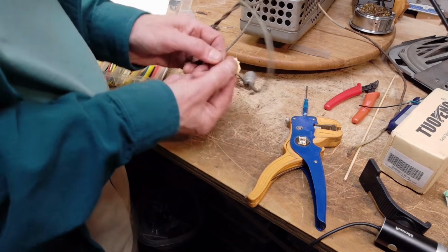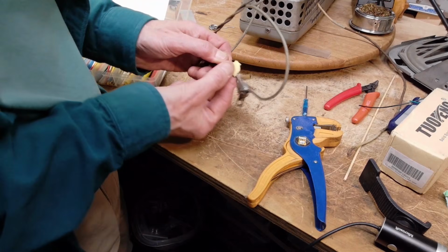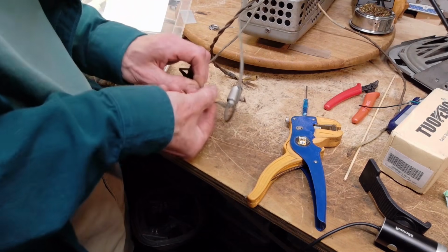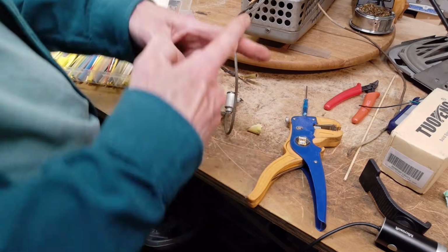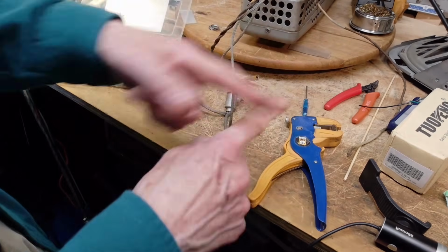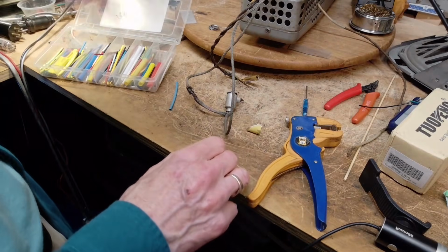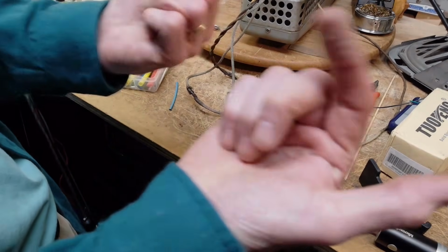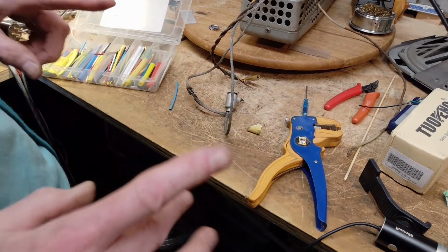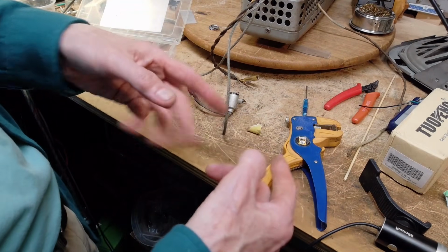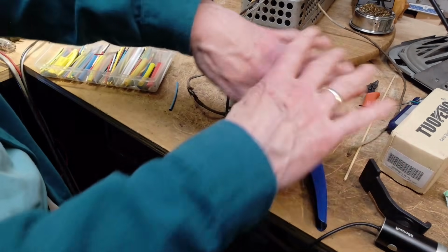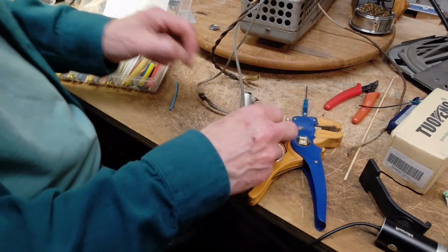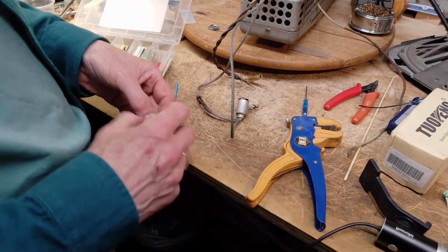So there's a system in the downtown of Toronto. It's called a network system. You have a network of low voltage cables going up and down the streets, all connected together like you see my fingers going - you can picture a network. They have buildings hooked up to it taking power out. They have transformer vaults dotted around it being fed with high voltage and then converting that to the low voltage to go onto the network. This is a very, very tricky way to distribute power.